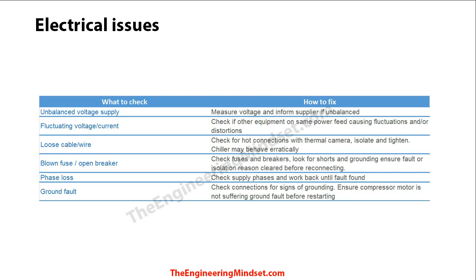Moving on to electrical issues: an unbalanced voltage supply is one common fault — measure voltages on each phase to confirm they're balanced. This could indicate a problem with the electrical switchgear within the building. Another common problem is fluctuating voltage or current, usually caused by other equipment on the same circuit creating distortions in the waveforms. The chiller may detect this and shut down as a precaution, particularly if there's a sudden inrush current from another plant item on the same circuit.